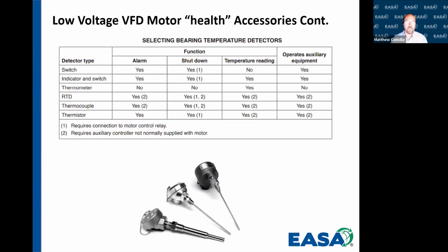The same thing is said for bearings. Now, one of the things that I saw for bearings a lot of times is that we thought we were doing a really good job of monitoring the bearing temperature by putting an RTD on the outer cap. Or in the instance of a white metal or a sleeve bearing, maybe we are monitoring the oil temperature. Well, that's great, and that does provide a relative term. In the instance of a white metal or sleeve bearing machine, if we have a large oil reservoir, we're not going to see a large change in temperature of the oil before the bearing gets hot. So it's always best, if we can, within reason, to actually get an RTD that you can sit either on the outer race of a roller element bearing or on the top of the bearing half on a white metal or sleeve bearing.